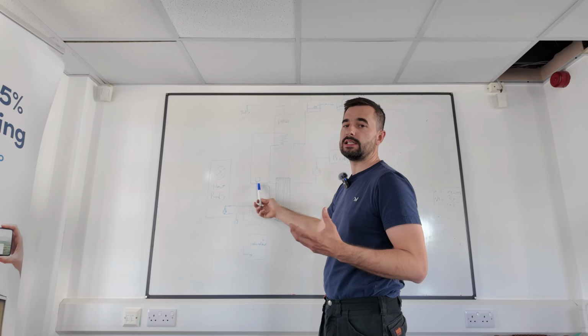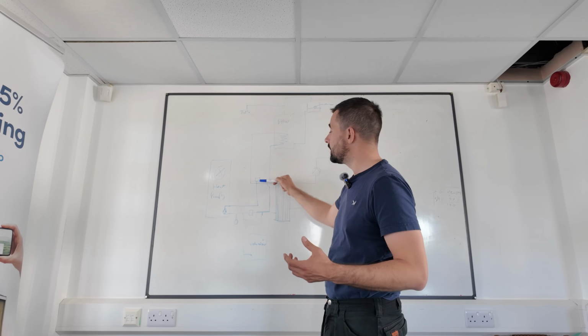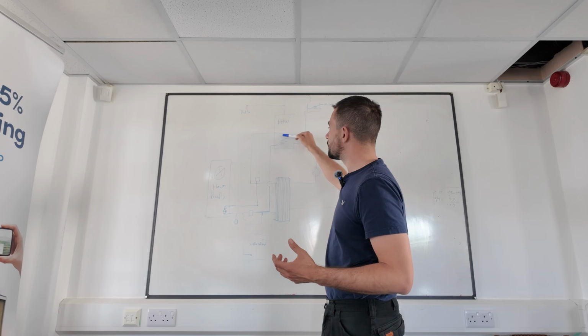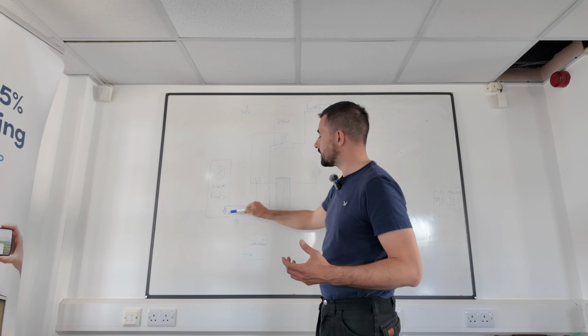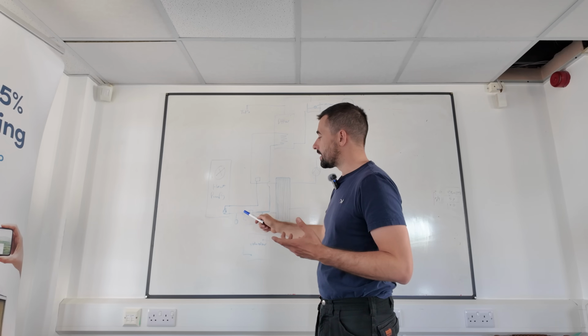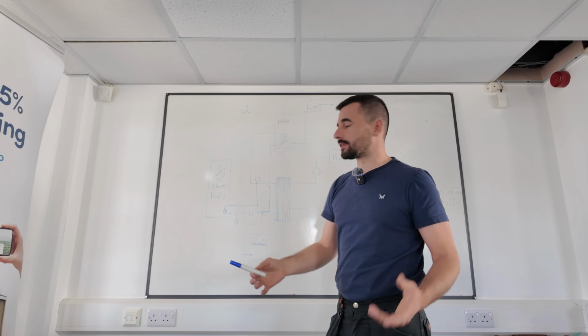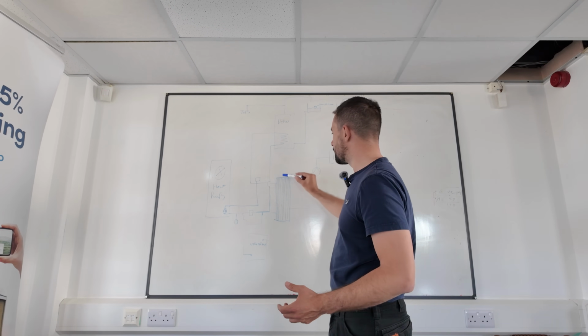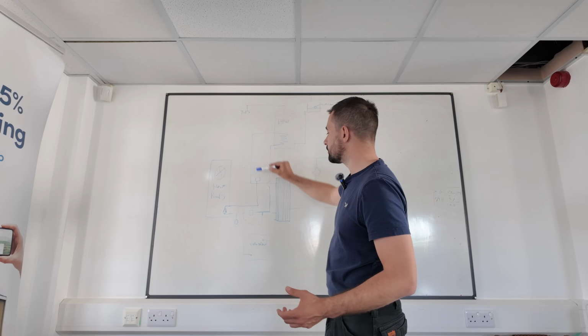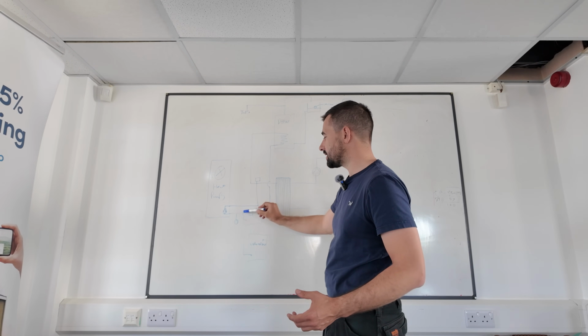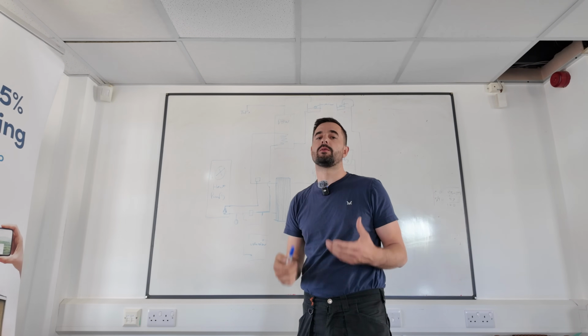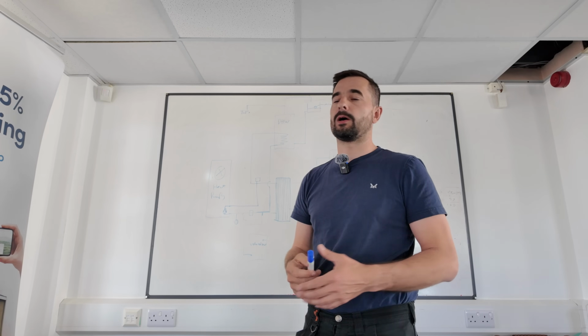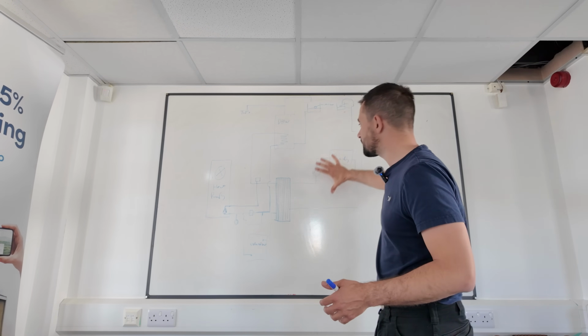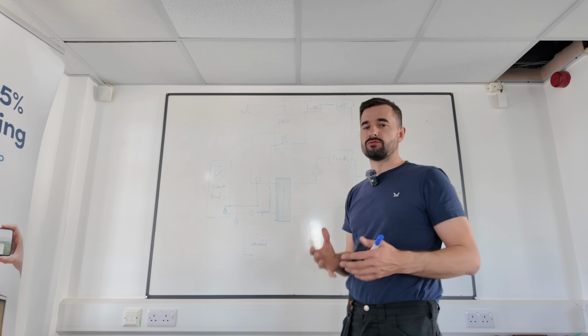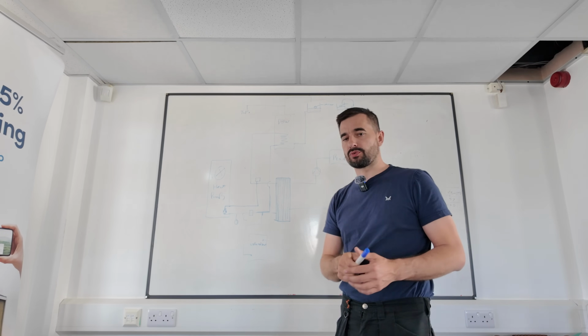Now, depending if it's doing heating or hot water, if it's doing hot water, it'll run through the cylinder coil, back to the heat pump via the filter, etc., back to the heat pump, and that's that. Now, all this pipe work and this heat exchanger and that coil is pressurized. It's got an expansion tank and a filling loop. That will be run between 1 and 1.5 bar. Now, this side of the system, the existing radiator system, we didn't want to pressurize.